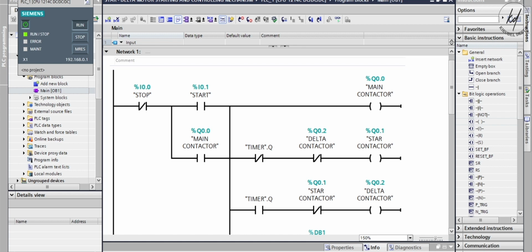This is a starting method that reduces the starting current and starting torque. The device normally consists of 3 contactors, an overload relay and a timer for setting the time in the star position, that means starting position. The motor must be delta connected during a normal run, in order to be able to use the starting method. The resulting starting current is about 30% of the starting current during direct online start, and the starting torque is reduced to about 25% of the torque available at a direct online start.